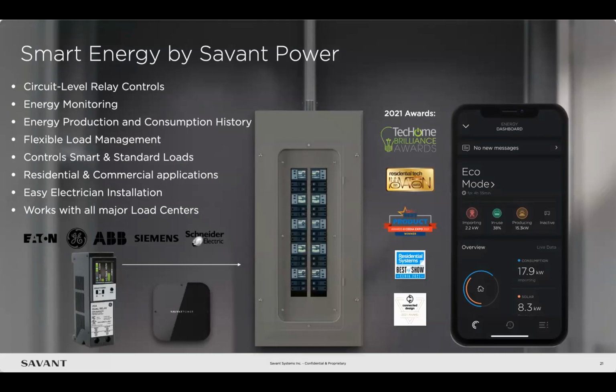Each individual module, for the 20 amp, has 2 circuits. The 30 amp has 1 circuit, and the 60 amp has 1 circuit. That's where we call this our flexible load management, so now we have independent control of entire circuits, one by one.